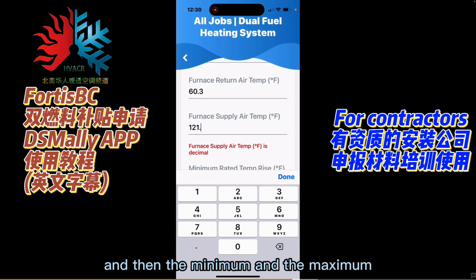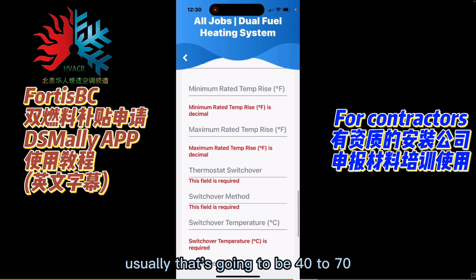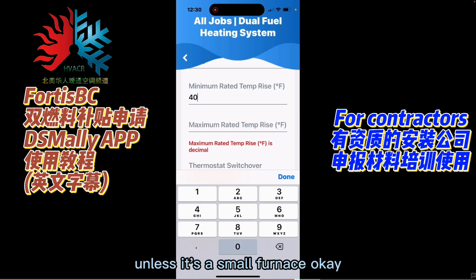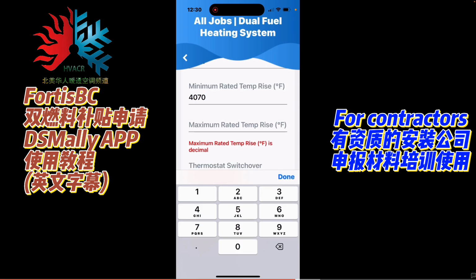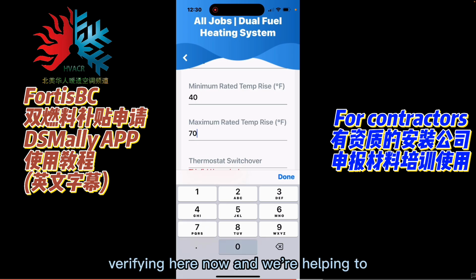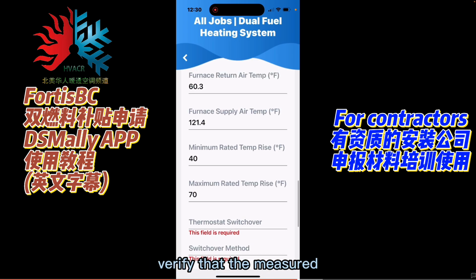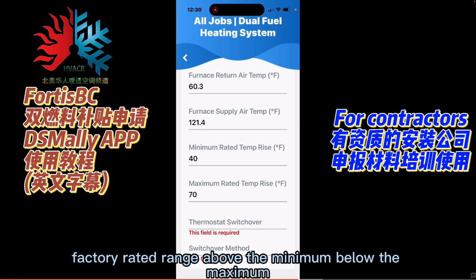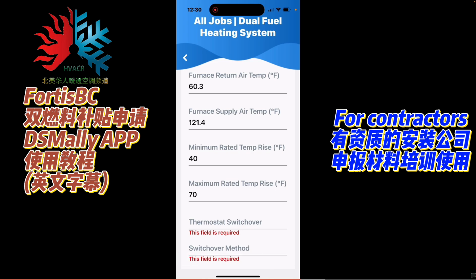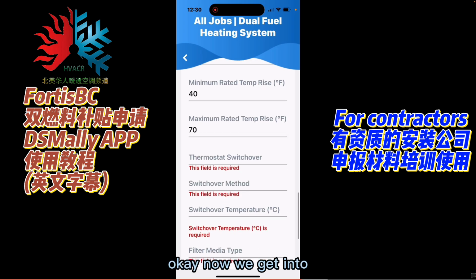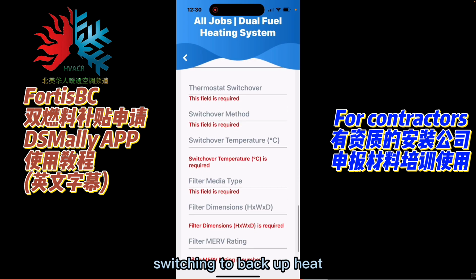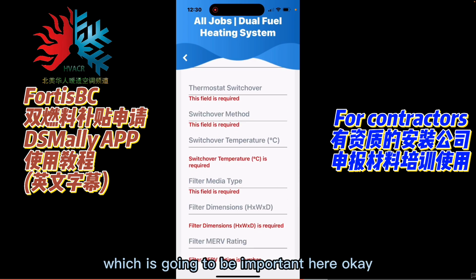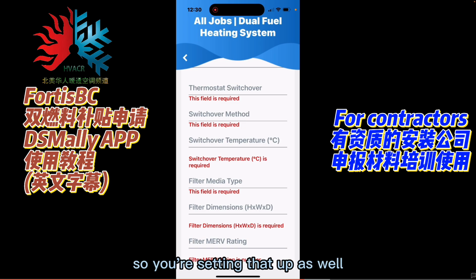And then the minimum and the maximum. Usually that's going to be 40 to 70, unless it's a small furnace, okay? And again, you're just verifying here, and you're helping to verify that the measured rise is within the factory rated range, above the minimum, below the maximum. Okay, now we get into switching to backup heat, which is going to be important here. So you're setting that up as well.